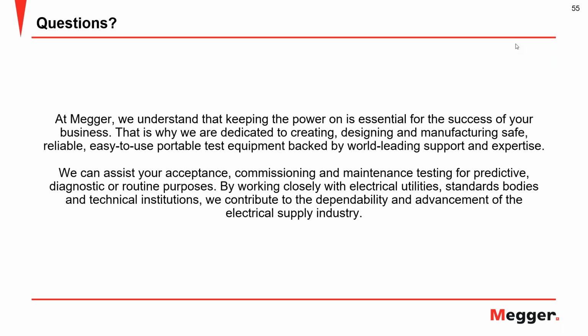All right, our next question is going to go over to Charles. Actually, it's not a question, it's more of a comment we got from Dennis. Dennis had mentioned that it is important to note that a transient could start a PDIV above normal line to ground voltage. So, if PDIV is below normal line to ground or even close to it, one would be in trouble. Charles, I know you wanted to have a comment on that.